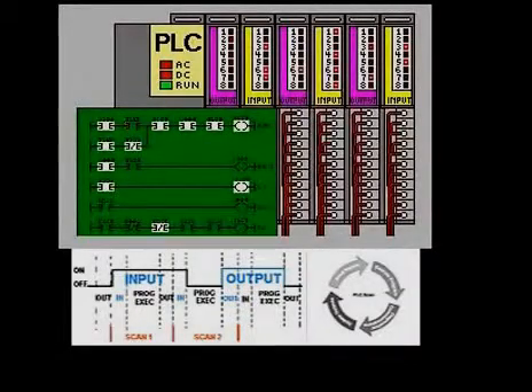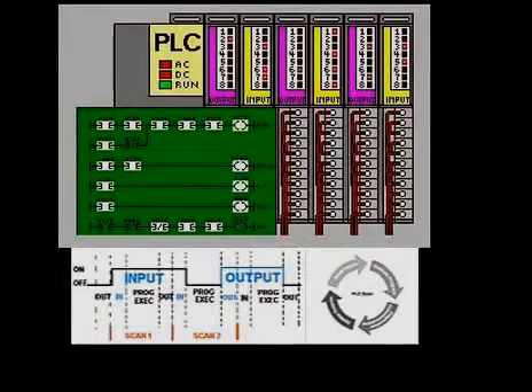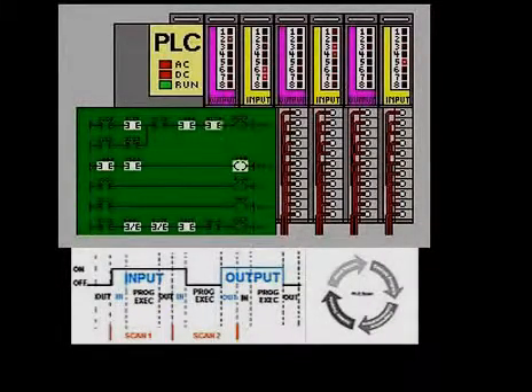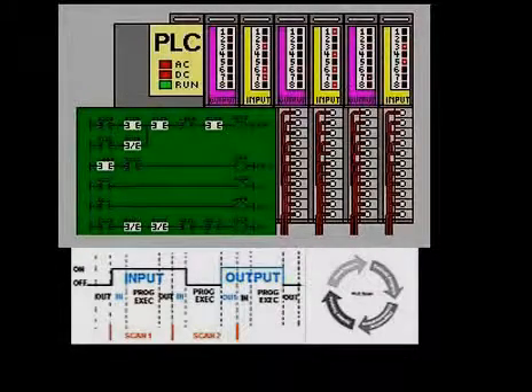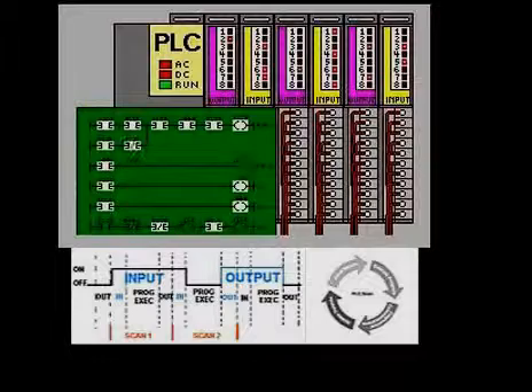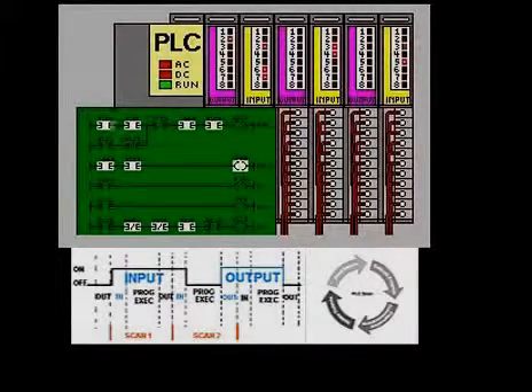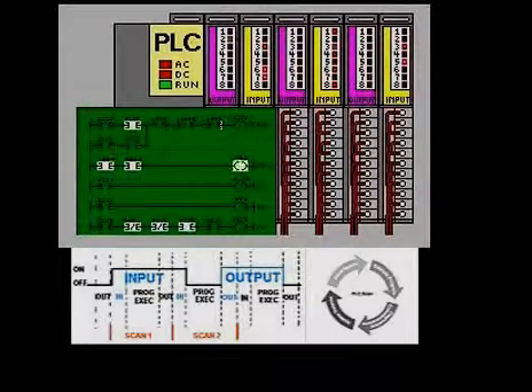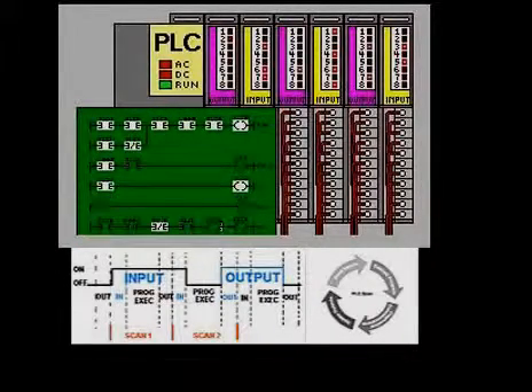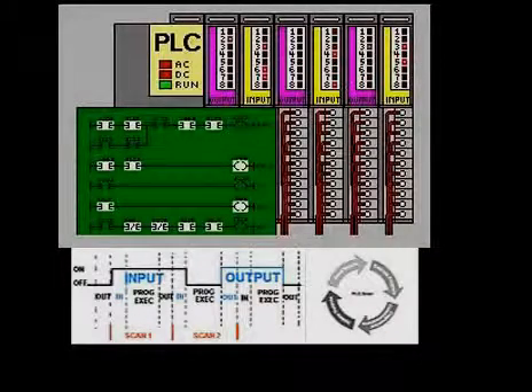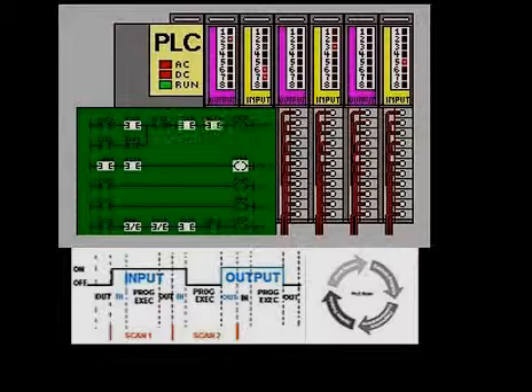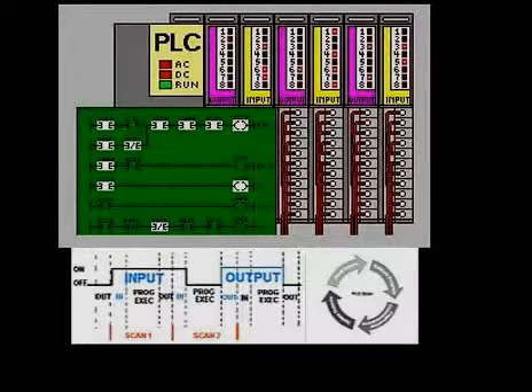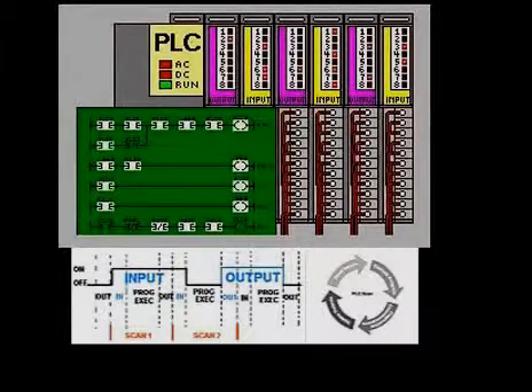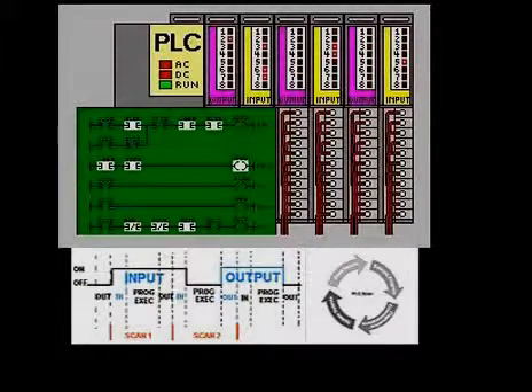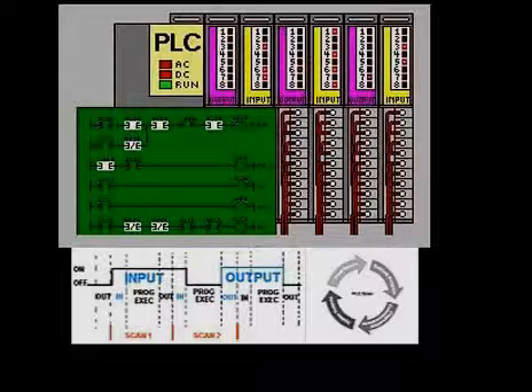A PLC works by continually scanning a program. It basically scans each ladder rung individually in the entire ladder logic program, updating the outputs on that rung after scanning through the inputs. A PLC program is generally executed repeatedly as long as the controlled system is running. The status of physical input points is copied to an area of memory accessible to the processor, sometimes called the I/O image table. The program is then run from its first instruction down to the last rung. It takes some time for the processor of the PLC to evaluate all the rungs and update the I/O image table with the status of the outputs.